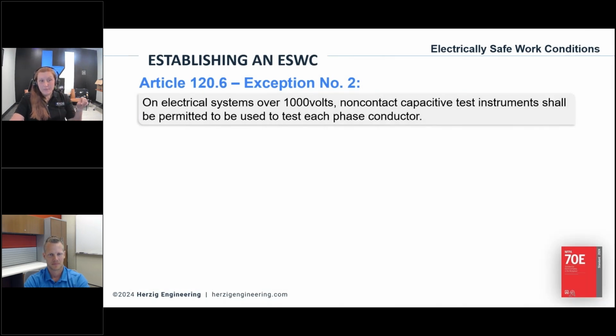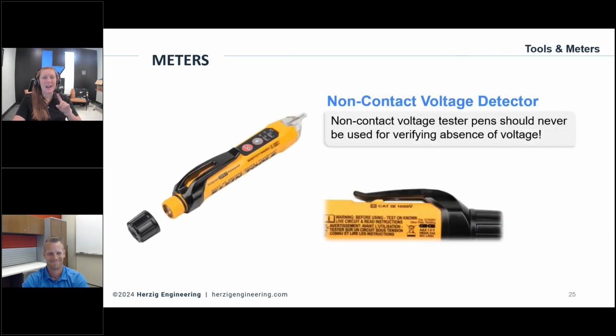There is another exception. So exception number 2 is about if it's over 1,000 volts. So we're talking more like medium voltage equipment at this point. You're not going to use a physical meter with the metal leads on the equipment. It's more going to be a capacitive test instrument that's non-contact, a proximity detector, for example, a nicely rated one that's designed for absence of voltage over 1,000 volts, not these little pen testers. Those are very different. Do not use these for verifying absence of voltage. I always have to clarify that because people get those mixed up. It's so easy to do, especially if you carry these around. I'm not even going to get into whether or not you should carry around these Widowmakers, but if you do, don't use them for verifying absence of voltage.